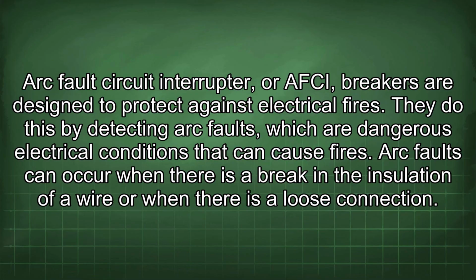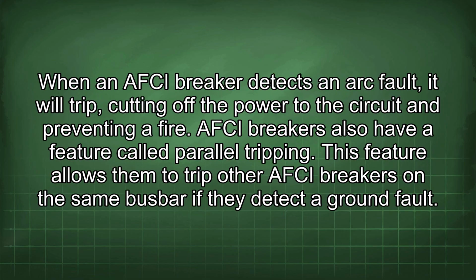Arc fault circuit interrupter, or AFCI, breakers are designed to protect against electrical fires. They do this by detecting arc faults, which are dangerous electrical conditions that can cause fires. Arc faults can occur when there is a break in the insulation of a wire or when there is a loose connection.